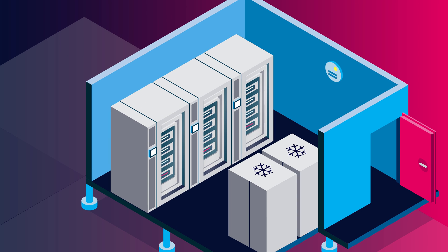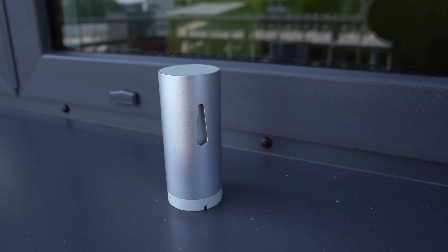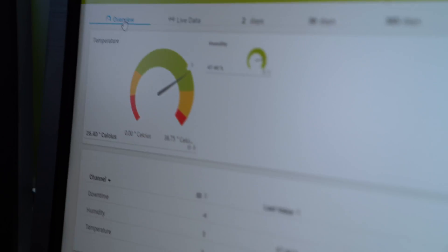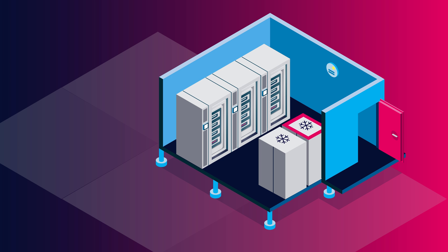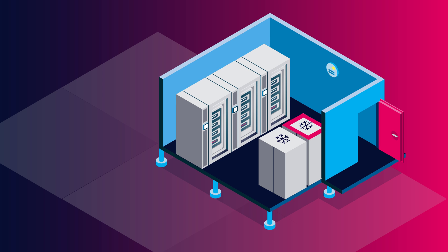So we added a third-party temperature sensor which we included in PRTG, so we could see what the temperature was in the data center. Even before the day of the incident, there were already some signs of the impending disaster. One day, we got a notification from PRTG that the temperature rose in the server room. We went there directly and found out that the main air conditioning system had a problem. The backup system started, cooled the server room down, stopped at the defined temperature, then the server room heated up again — it was like a cycle.